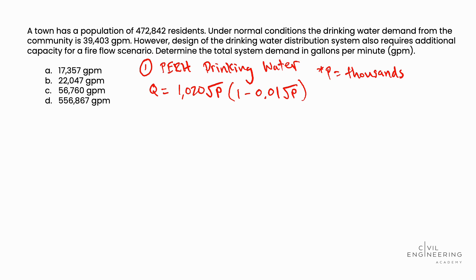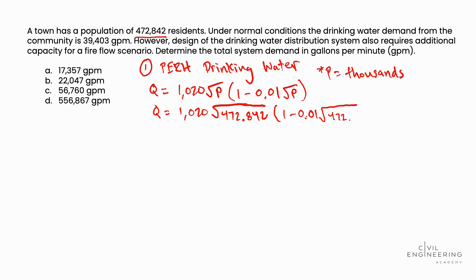We're going to look back at the problem statement to solve this. Q, the fire flow rate, is equal to 1,020 × √P, where P is the population in thousands. In the problem statement, we're told 472,842 residents, so we divide that by 1,000 to get P = 472.842. Performing this calculation, we determine that the fire flow rate is equal to 17,356.841 gallons per minute.